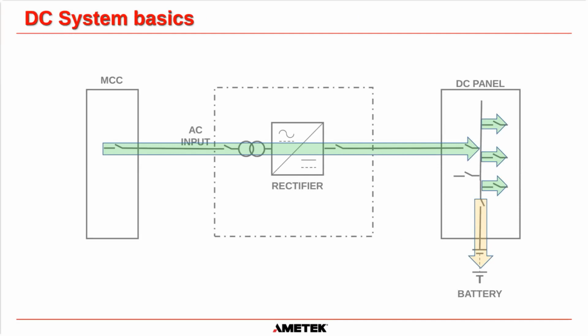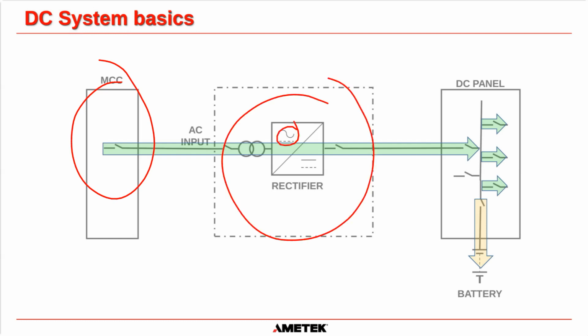So here is the most basic version of a DC system. And this is actually my preferred way for people to connect systems when they're out in the field. Obviously on the left-hand side here, you have your MCC. That's going to supply AC to your rectifier or your charger. Then that rectifier converts the AC here into DC. And then that goes out to a DC panel. And that DC panel has our load circuits connected here. And then down at the bottom, we also have a circuit for our battery.